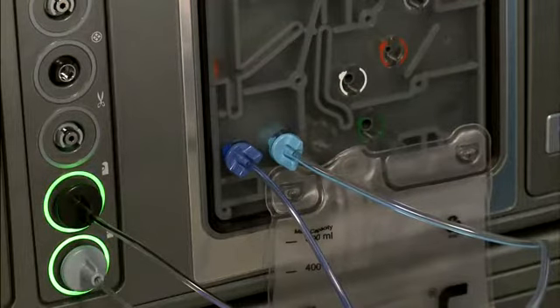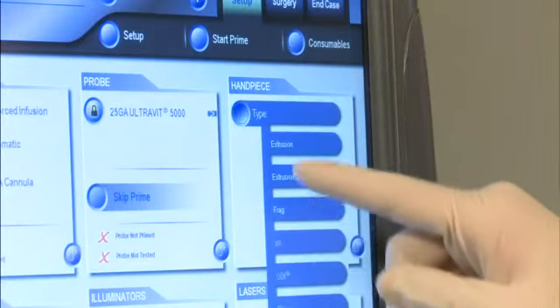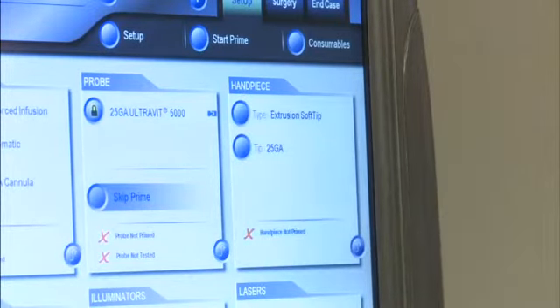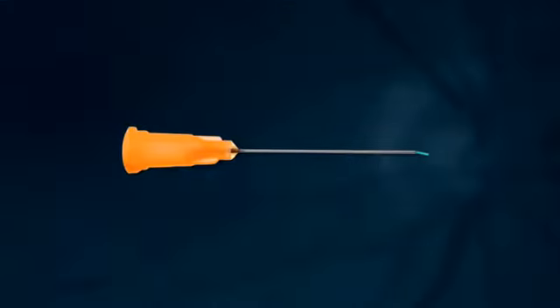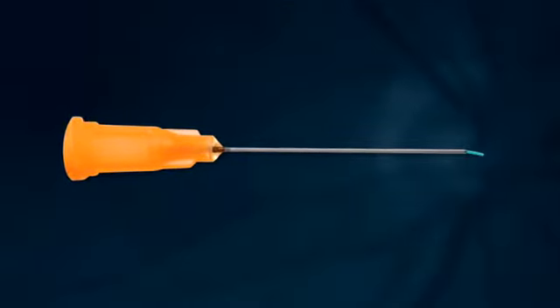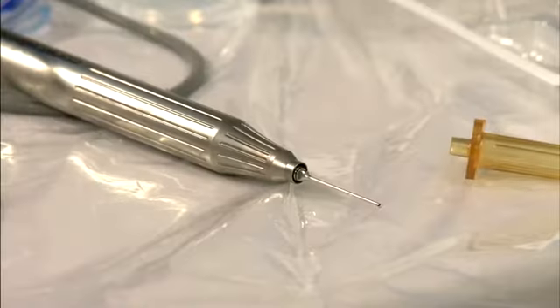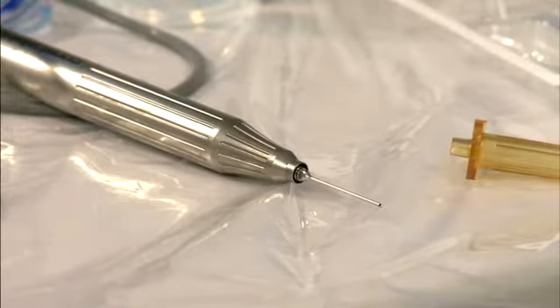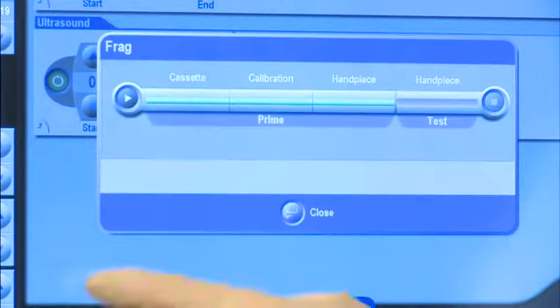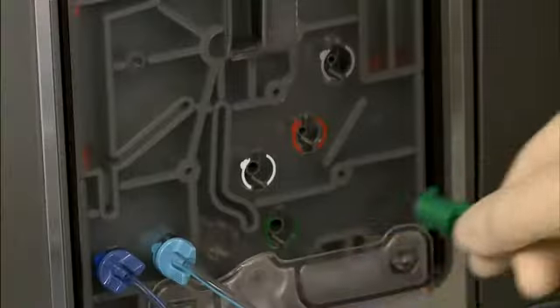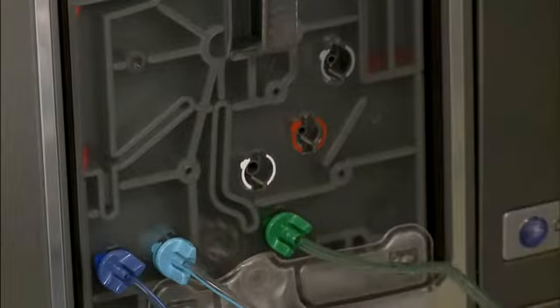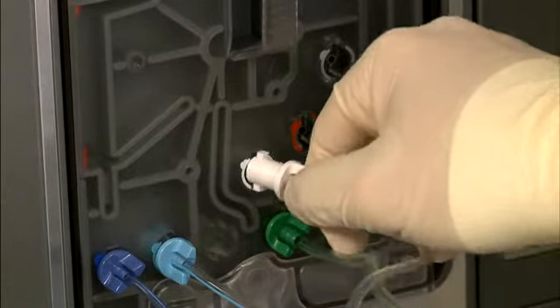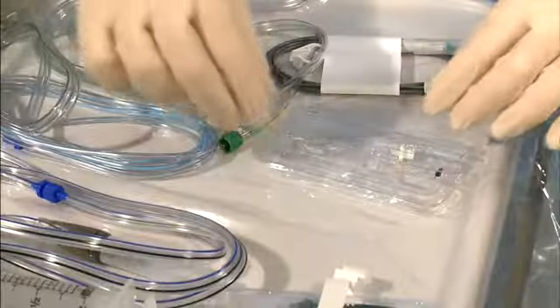Connect the light blue extrusion line to the cassette. Then select Extrusion Soft Tip from the handpiece drop-down menu bar. Now attach the soft tip needle to the extrusion line. If a fragmentation handpiece is used, please refer to the Constellation System Fragmentation section later in this video. Connect both the green and white connectors of the infusion tubing set to the cassette.